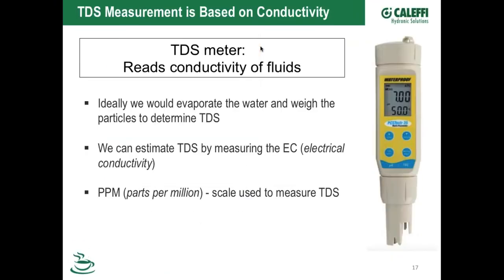So by knowing the conductivity of the water, that tells us a couple things. The more minerals or stuff in your water, the higher the conductivity, the higher the TDS. The higher the conductivity, the more potential for corrosion, because that water can carry enough current to cause galvanic corrosion—basically forming a battery in your system. If you've got high conductivity and mixed metals like copper, iron, steel, or zinc, those metals will react to one another based on the conductivity of that water. So if we strip all that stuff out of the water and get it down to a very low TDS, we won't have issues with galvanic corrosion.